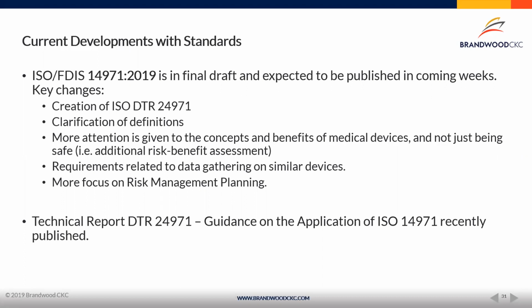Typically, or previously, that content was kind of woven into the standard itself. Now it's an external document. It's very similar to other documents or other standards in the space, but it gives you that guidance, the ability for you as a manufacturer to understand how you're going to apply 14971 to your medical device.